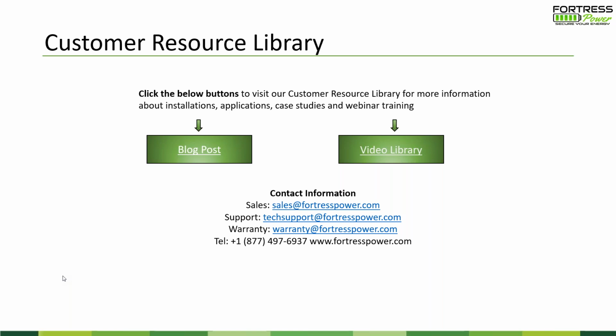For the continuous output of the eVault, just refer to the spec sheet — it's about 8.5 to 9 kW. We design our batteries to be 2-hour batteries, so the rule of thumb is to take the battery capacity and divide by the maximum inverter output. If that benchmark is 2 hours or longer, you're in the appropriate range.